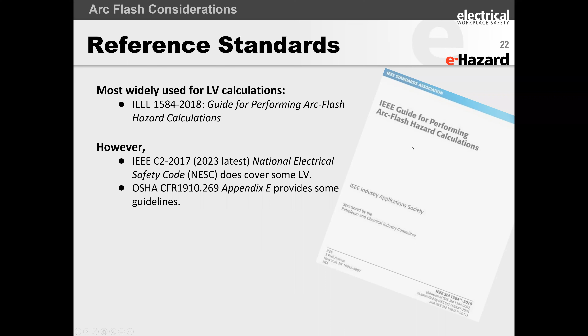So you also have the option to use the NESC and 1910.269 Appendix E. However, most low voltage folks default to software. There are 3 very famous software packages that are used: EasyPower, SKM Power Tools, and ETAP. Any one of those 3 systems implements the IEEE 1584 standard for your arc flash calculations. Now for high voltage, once you start getting above that 15 kV, the 1584 model, the IEEE equations, start becoming overly conservative. Because of that, OSHA recommends that we use ArcPro. It's a proprietary software that's based on some empirical work that was done at the Kinetrics laboratory out in Toronto.